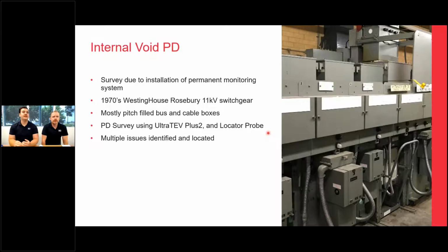This particular gear was actually 1970s Westinghouse Rosebury 11 kV switchgear. And the reason we were there is it was mostly pitch filled bus and cable boxes, which the client had identified as a risk to their network.